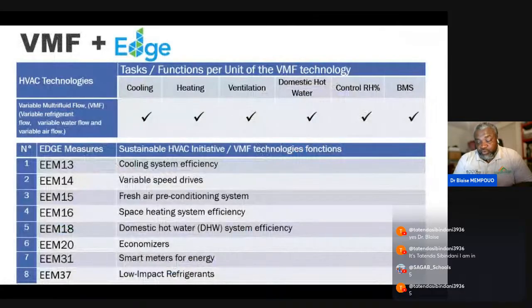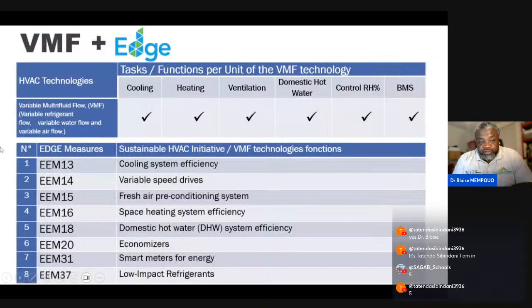Then I move on to modeling. I try to model the same condition with EDGE to see how we achieve the same saving. Like I mentioned before, with VRF we can achieve at least 8 measures in EDGE. This is the modeling I did. The measures are: cooling system efficiency, variable speed, fresh air preconditioning system, space heating system efficiency, domestic hot water, economizer, smart meter for energy, and low impact refrigerant.